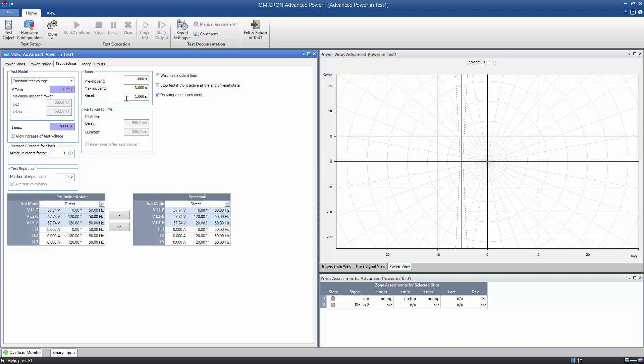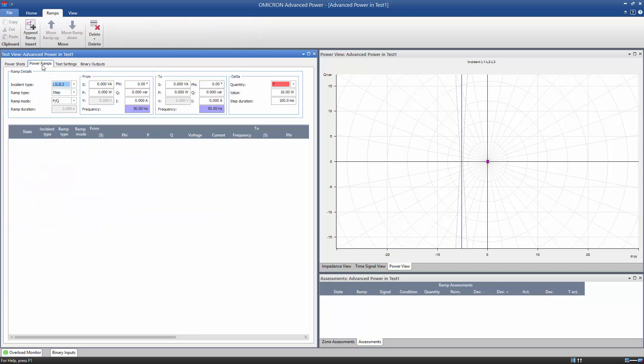For testing the pickup value of the reverse power function, we define a power ramp in the Power Ramps tab. We choose the incident type L1, L2, L3, the ramp type Step, and the mode PQ.